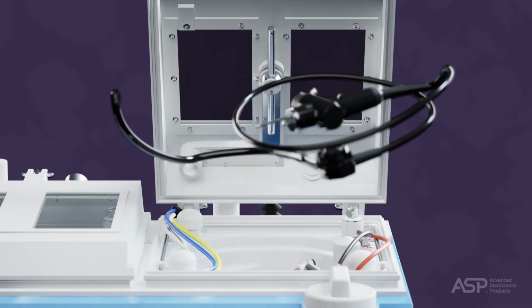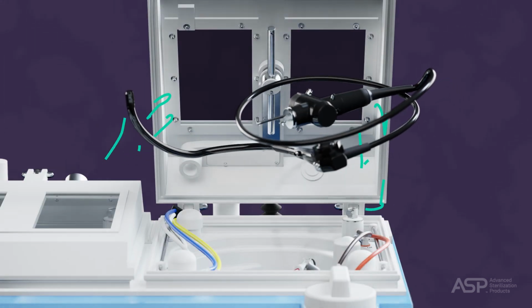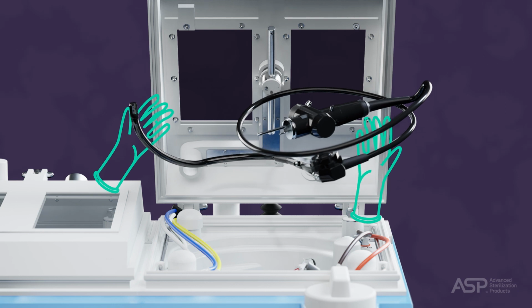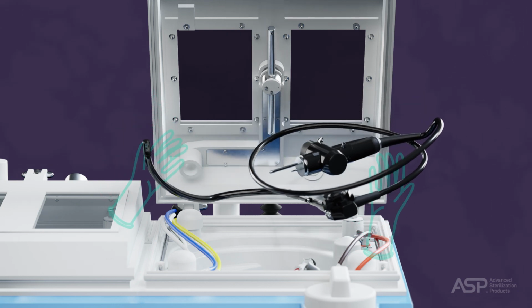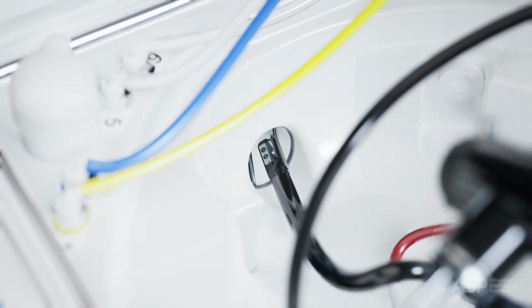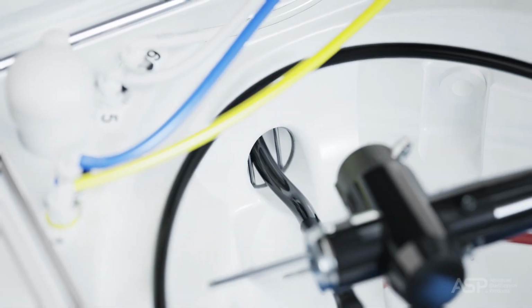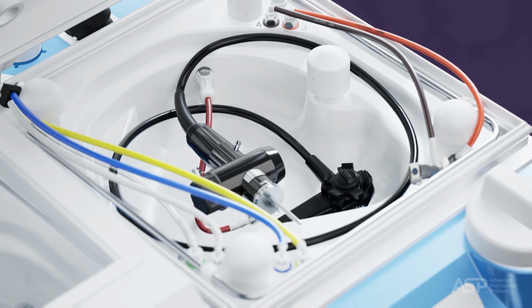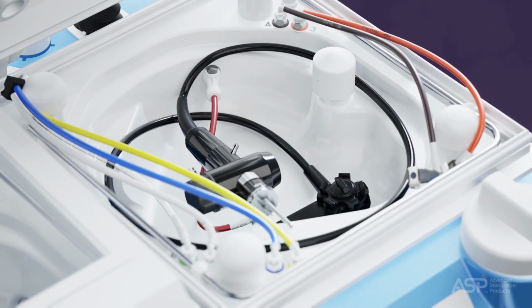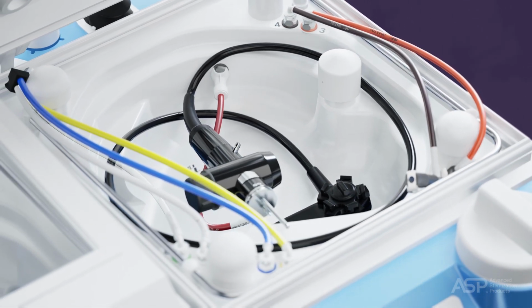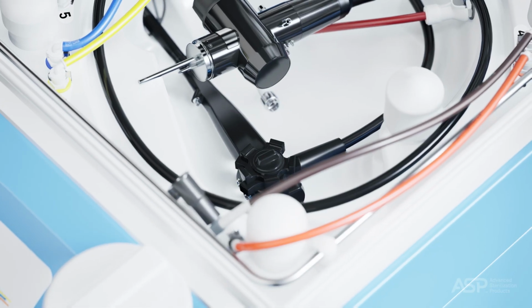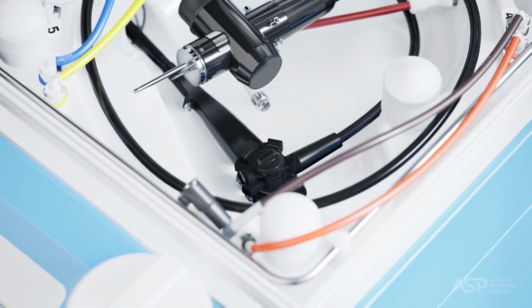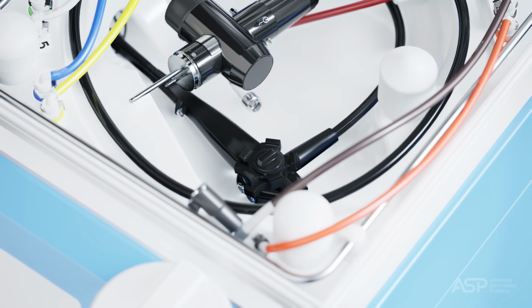For proper handling and loading of an endoscope, hold the distal end of the endoscope in one hand and the umbilicus loosely coiled in the other. Guide the insertion tube gently through the 2 metal bars that lead to the helical tubing in the basin. Position the endoscope head in the basin so that the umbilicus is loosely coiled and resting on the basin edge. The head of the endoscope should be gently placed with the knobs facing up to prevent unnecessary stress.